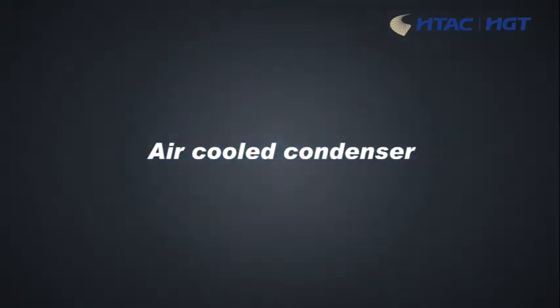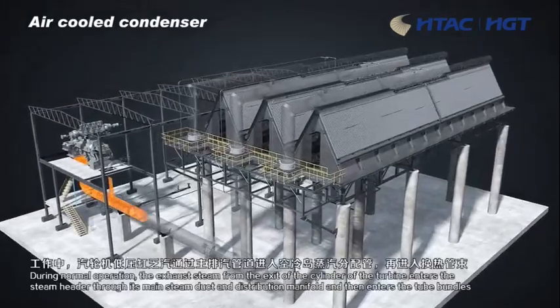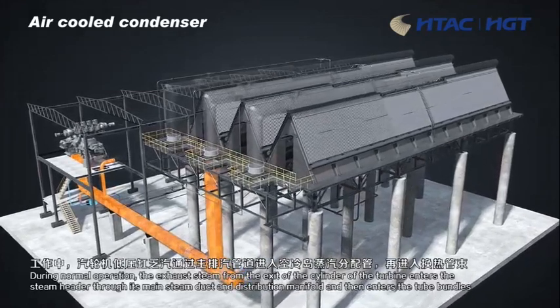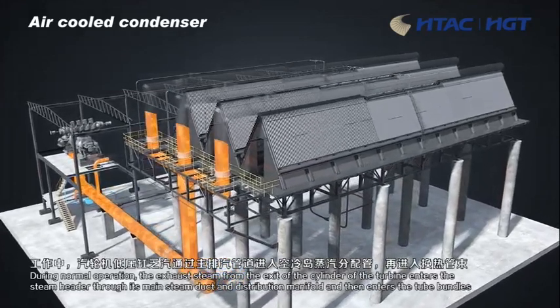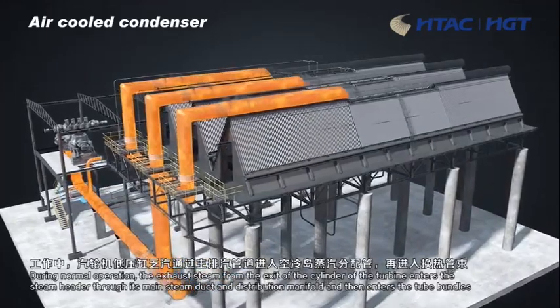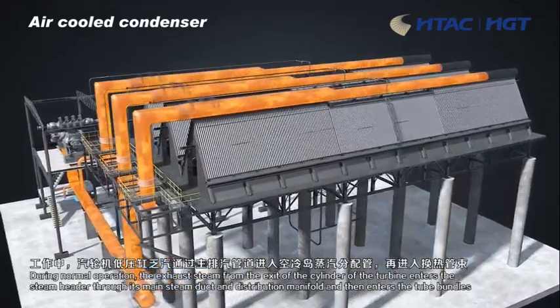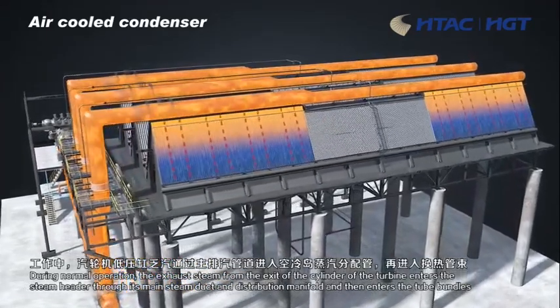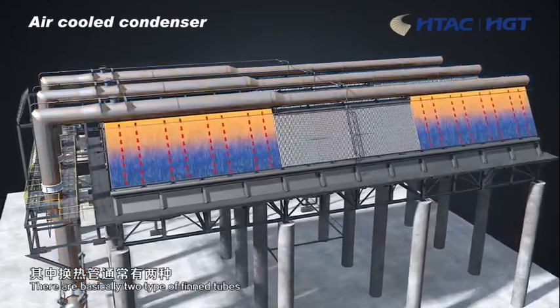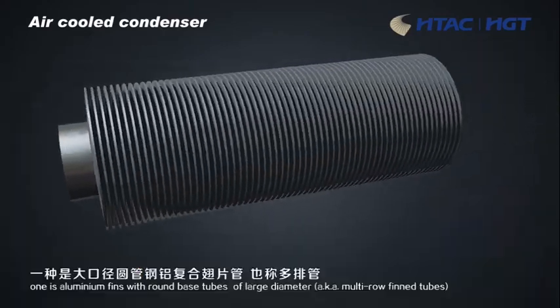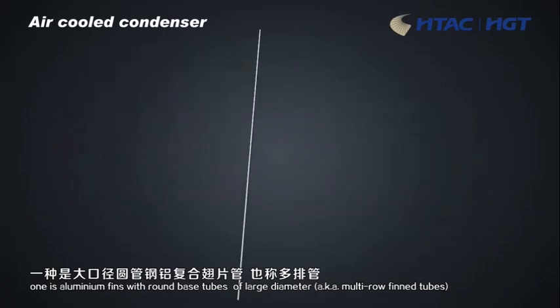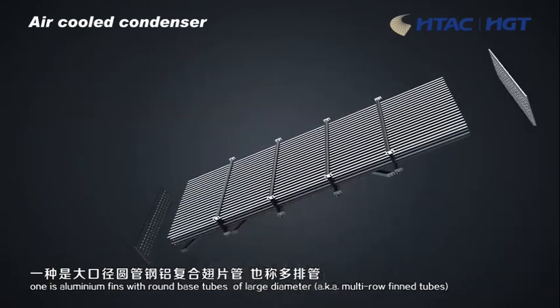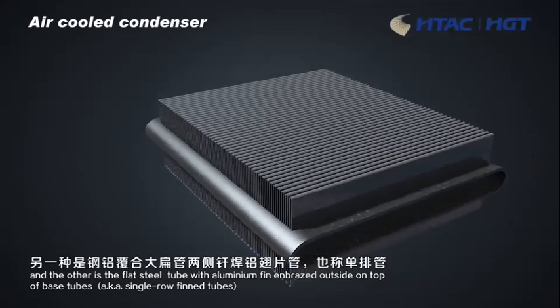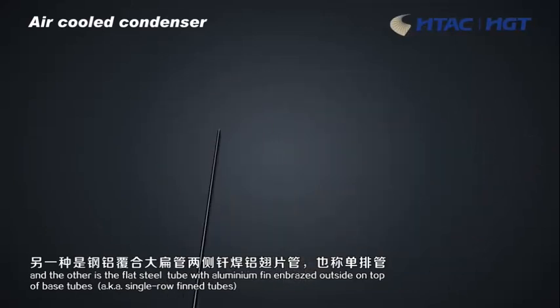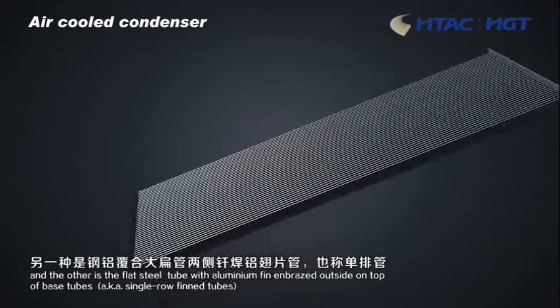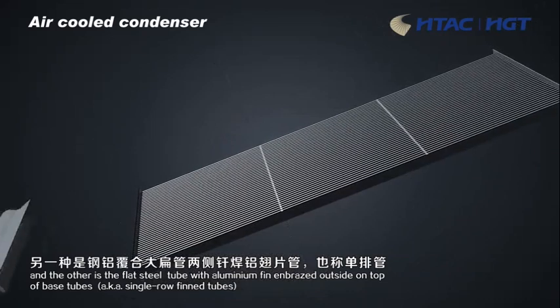Air-cooled condenser. During normal operation, the exhaust steam from the exit of the cylinder of the turbine enters the steam header through its main steam duct and distribution manifold, and then enters the tube bundles. There are basically two types of fin tubes. One is aluminum fins with round base tubes of large diameter, aka multi-row fin tubes, and the other is the flat steel tube with aluminum fin embraced outside on top of base tubes, aka single-row fin tubes.